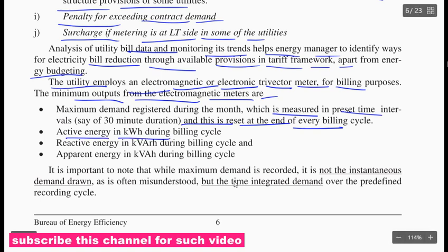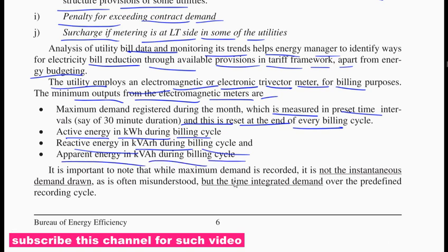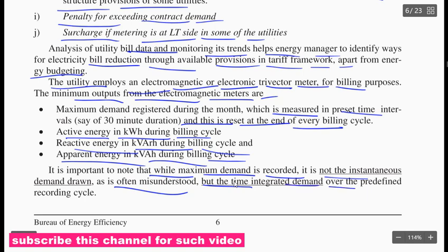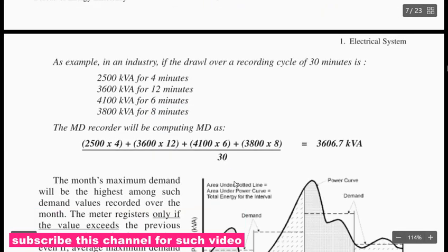Active energy in kWh during the billing cycle, reactive energy in kVARh during the billing cycle, and apparent energy in kVAh during the billing cycle. It is important to note that while maximum demand is recorded, it is not the instantaneous demand drawn. It is often misunderstood, but it is the time integrated demand over the predefined recording cycle.